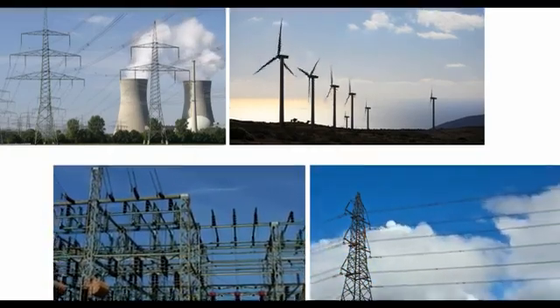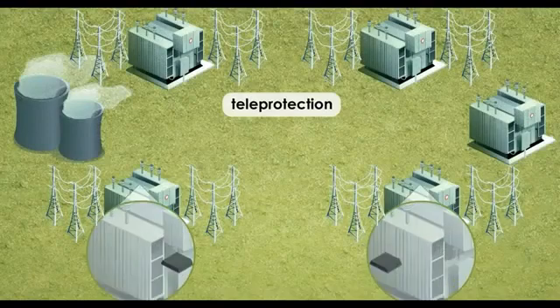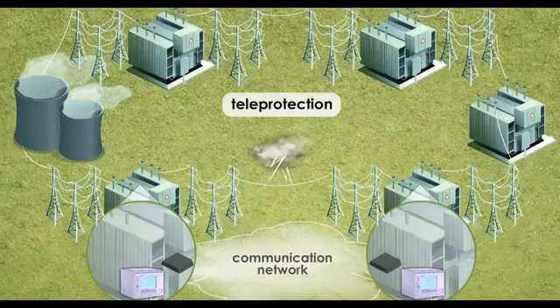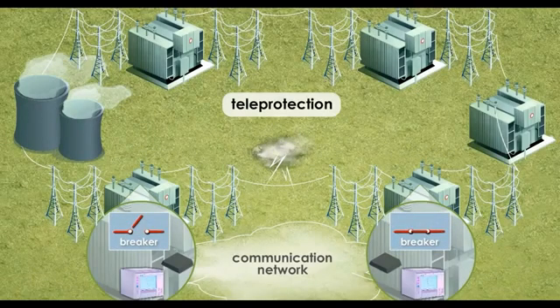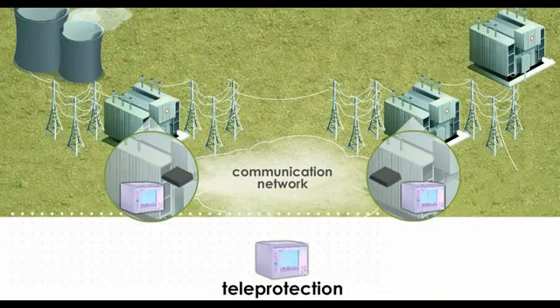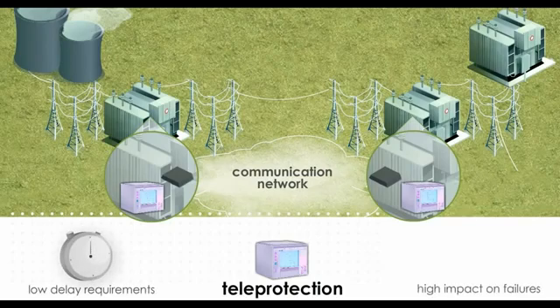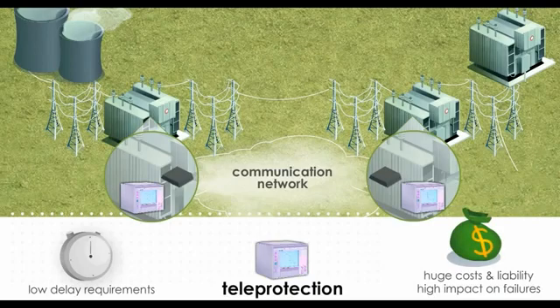An essential requirement for operating and maintaining a reliable, robust and safe electric grid is teleprotection. It involves relays that communicate with each other over a communication network to determine the presence of faults and trip the breakers to protect the grid and contain the impact of the fault to a localized region. Teleprotection is the most stringent application that can be transported over utility communication networks due to its very low delay requirements and the resulting impacts of a failure such as electricity outages or potential equipment damage, both generating huge costs and associated liability.